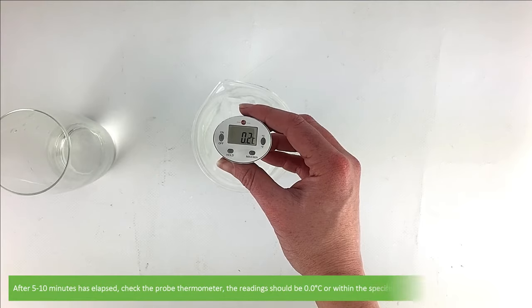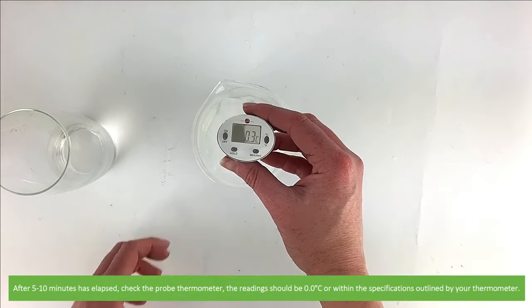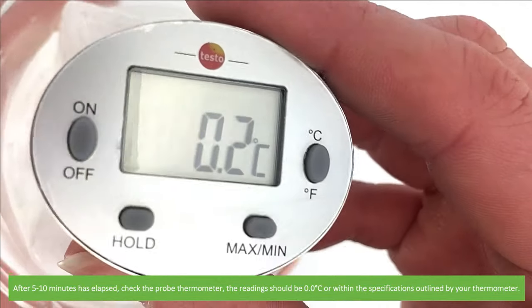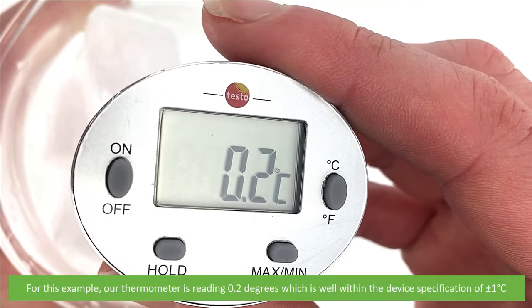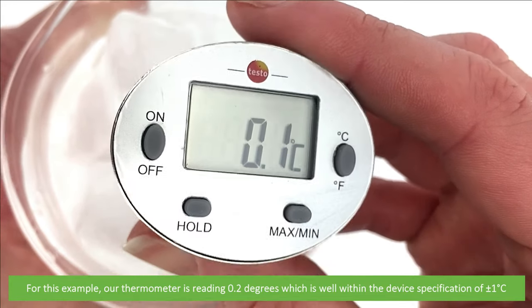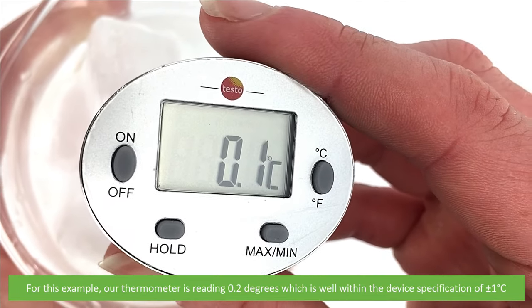After five to ten minutes has elapsed, check your probe thermometer. The reading should be zero degrees Celsius or within the specifications outlined by your thermometer. For this example, our thermometer is reading 0.2 degrees, which is well within the device specifications of plus or minus one degree Celsius.